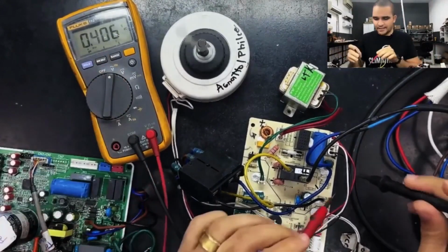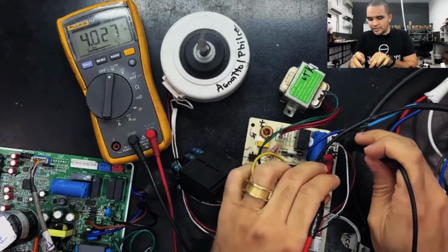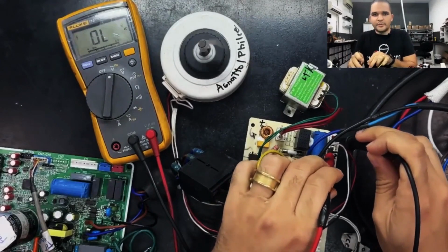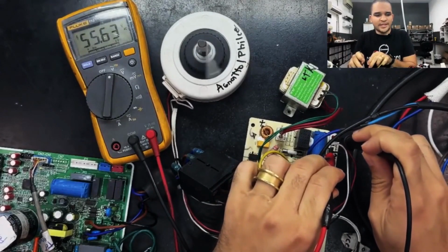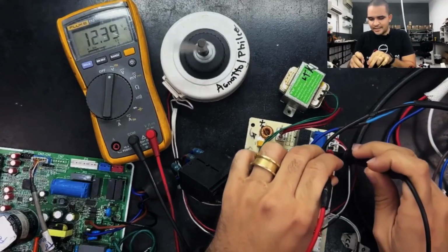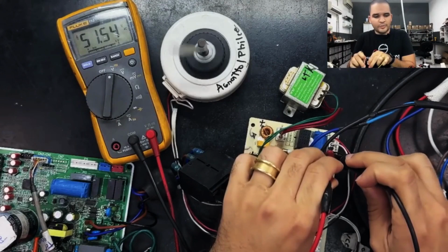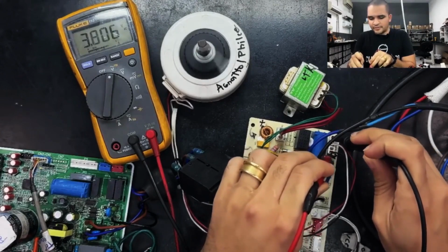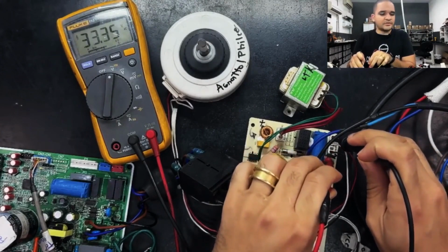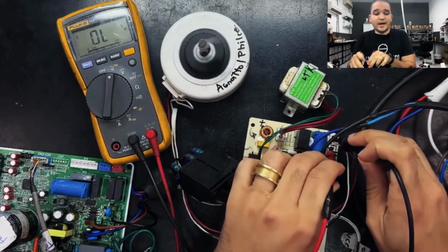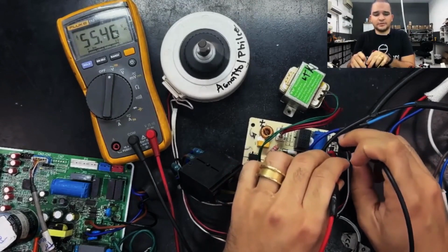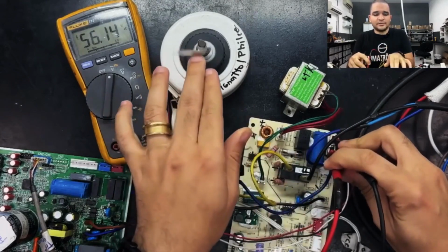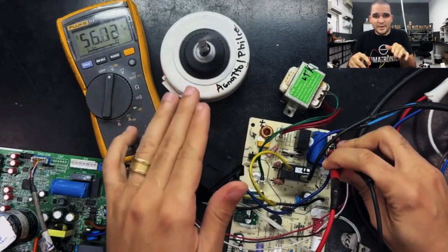Alternating current voltage. At the fan connection pins, it's rotating, correct. From the red wire to the white wire, it is providing 55 volts of alternating current. From the white to the black wire, it reads 51 volts, and from the red to the black, it reads 33 volts. Notice the voltage is low. It's not meant to be 220 volts. The modulation is slow, and I'm not sure if you can see it's running slower now.